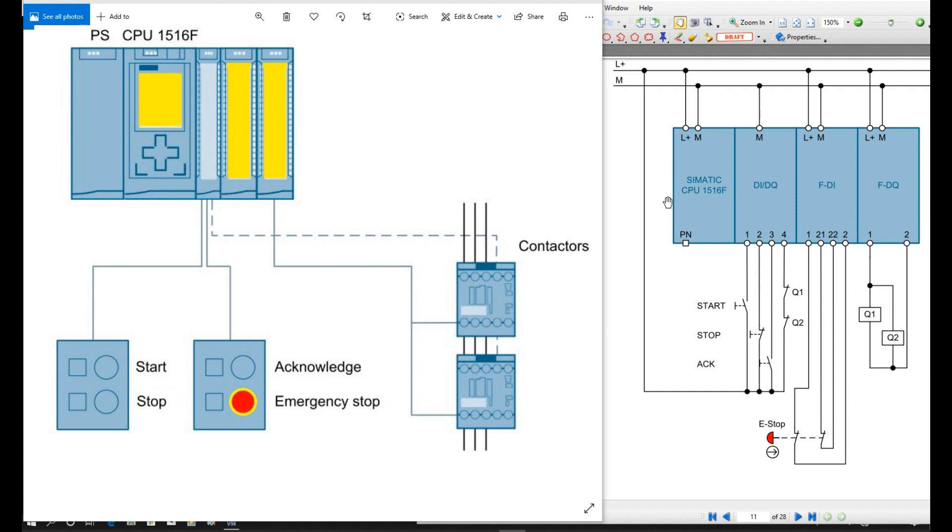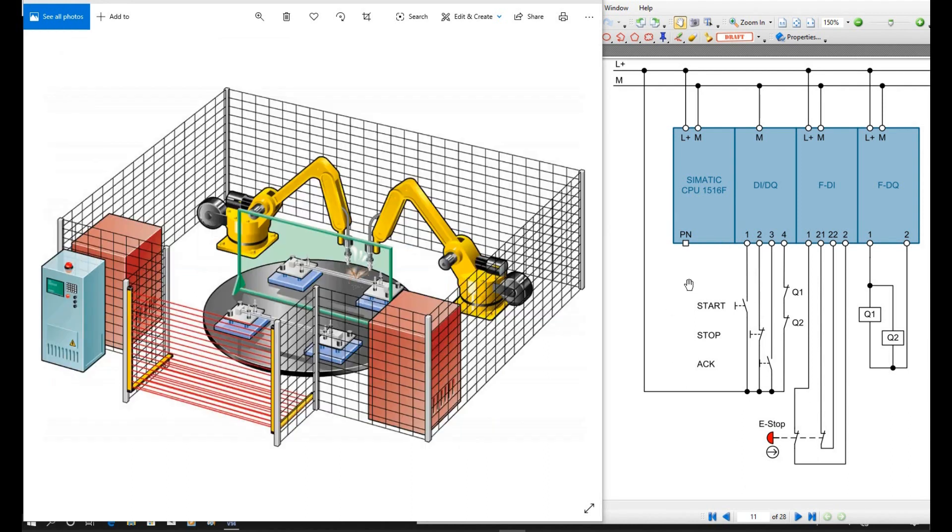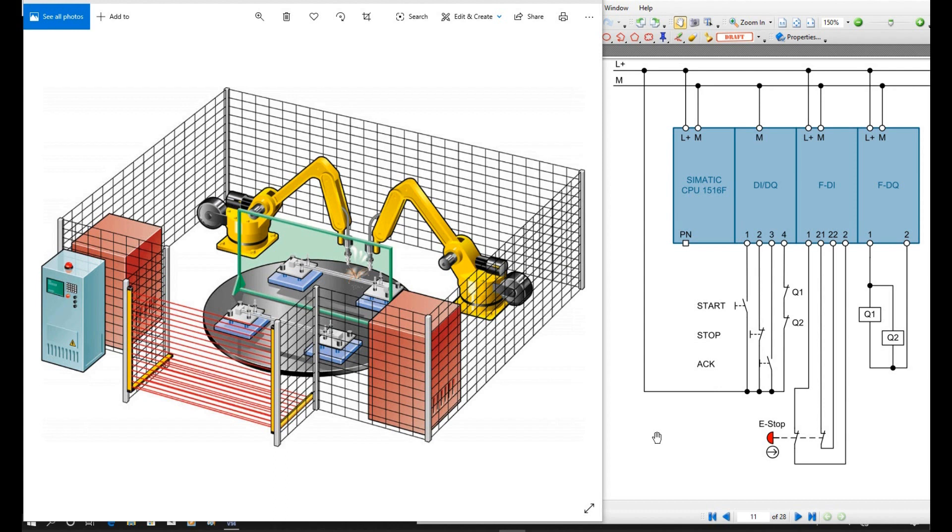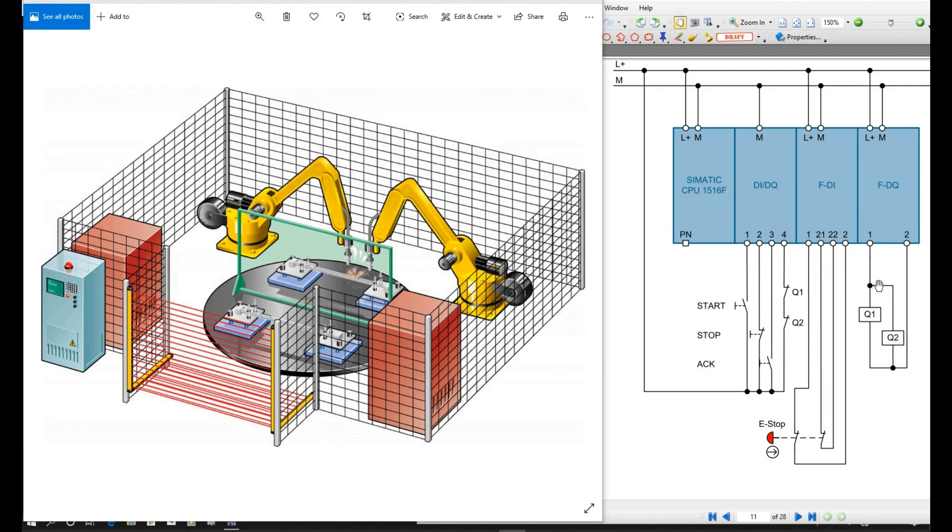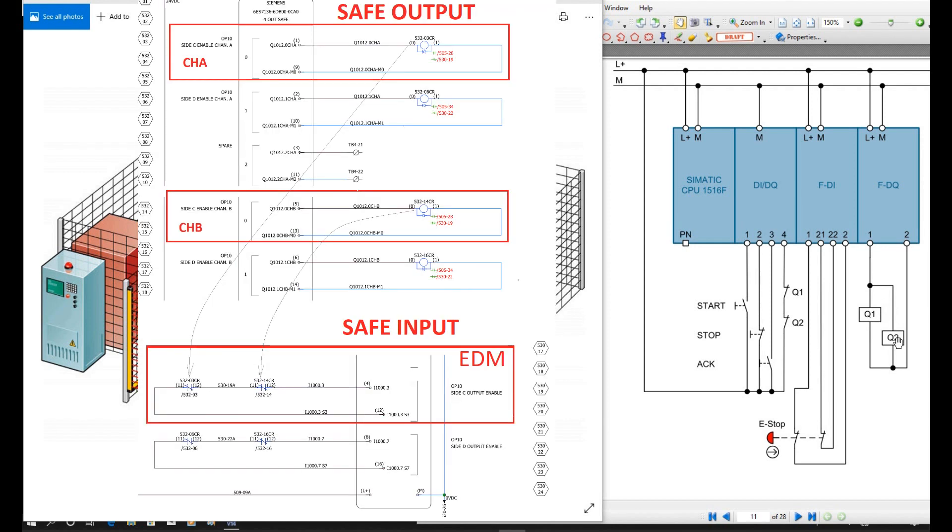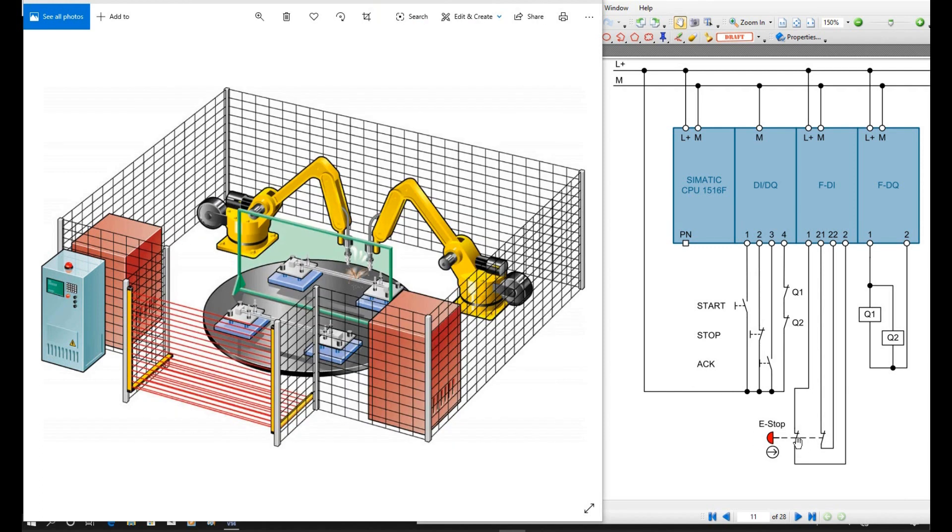On the right side, that is one typical control system with an E-stop safety function. For example, on the main control panel, it has three main buttons: start button, stop button, and acknowledge button, as well as one E-stop mushroom button. For the E-stop button, usually it has two circuit loops that go back to the safety input module. Once the E-stop is pressed, we will control the safety output two relays to disable the power or stop the output controlled by these safety relay outputs. The acknowledge button is usually used after the E-stop is recovered and released. After we hit this acknowledge, the output from this safety output module will be enabled again.